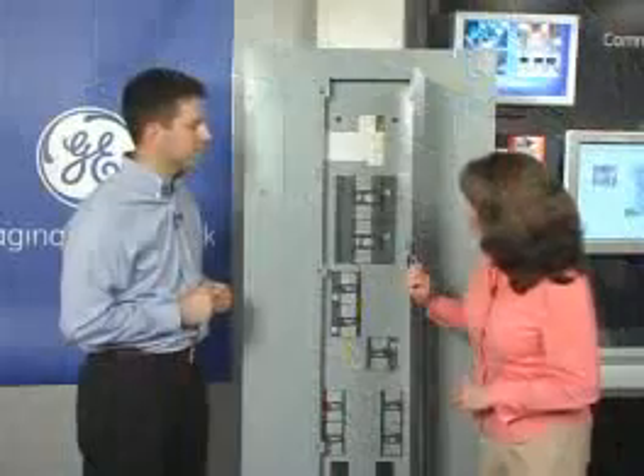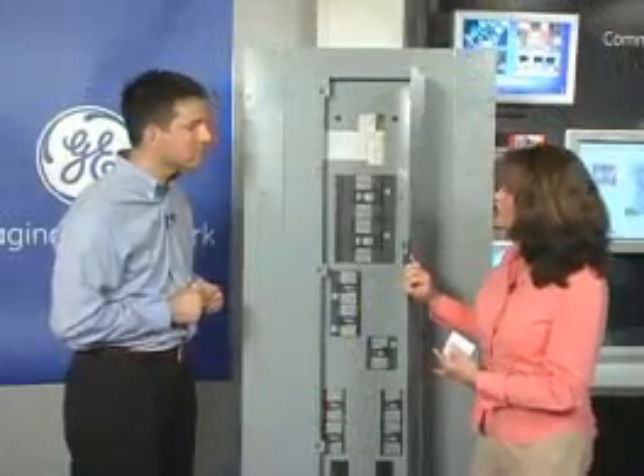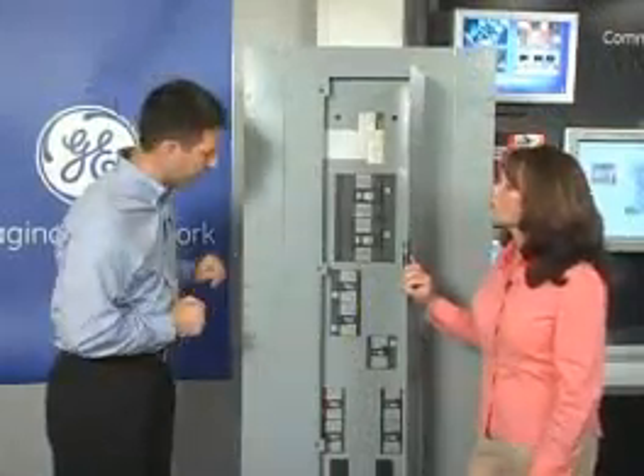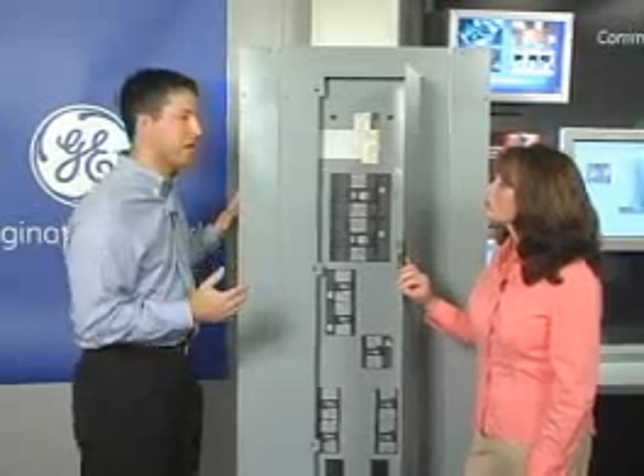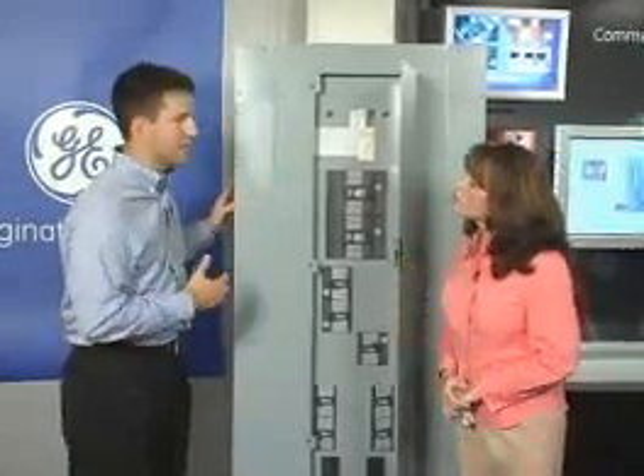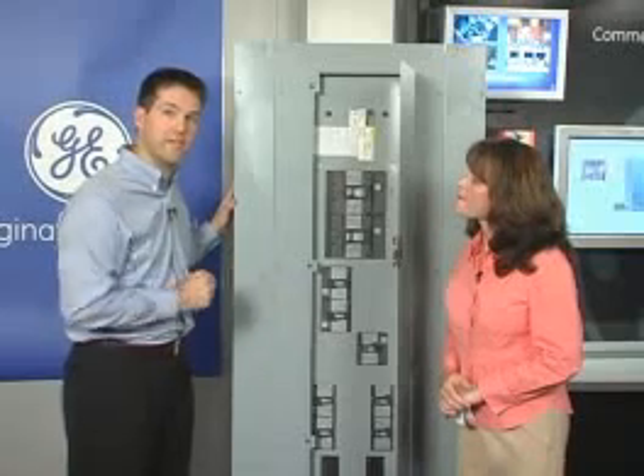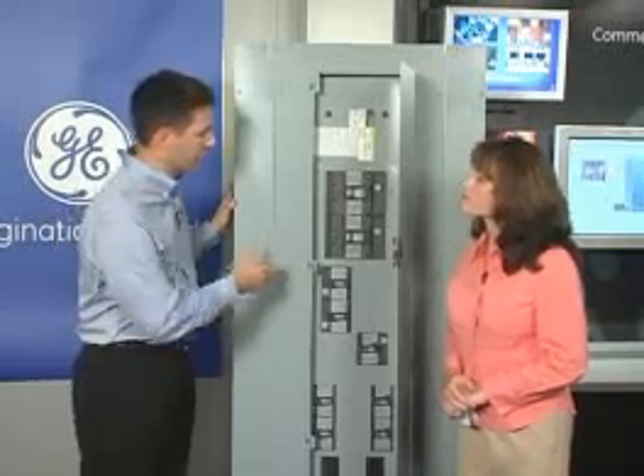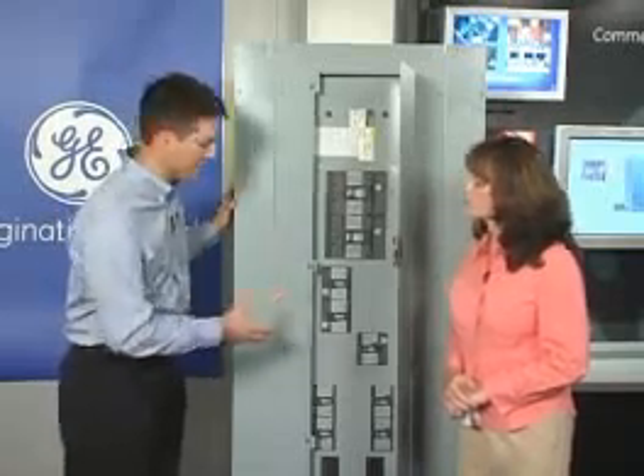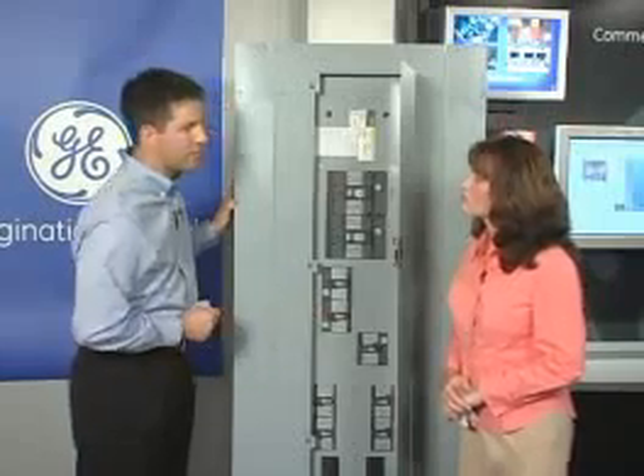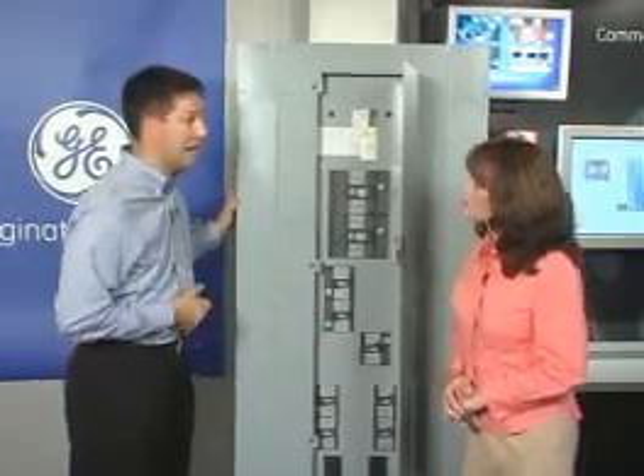Are these panels designed to handle future expansion? Of course. Like our traditional power distribution panel, we've allowed customers to put in breaker spaces at time of order. If you know you'll need an 800 amp breaker or a 250 amp breaker, you can add the space right up front, and we'll put all the hardware in there so you can add it later.